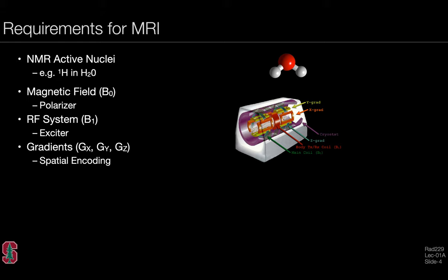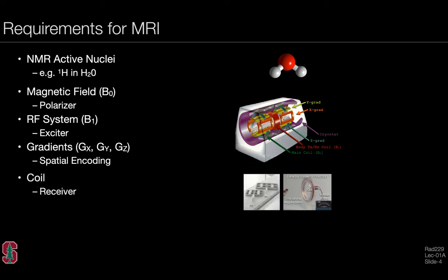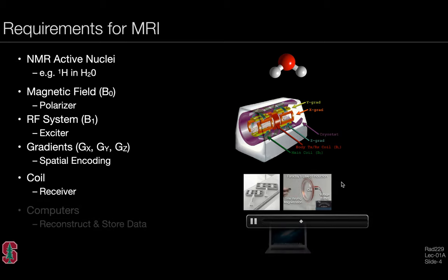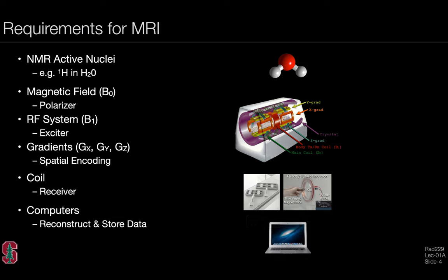We also need gradients, the GX, GY, and GZ gradients, whose principal function is spatial encoding. Finally, we need coils or receivers that are available for detecting the transverse magnetization according to Faraday's law of induction. And needless to say, there are several computers involved that are required for reconstructing and storing the data.